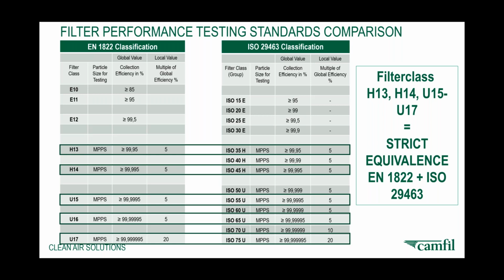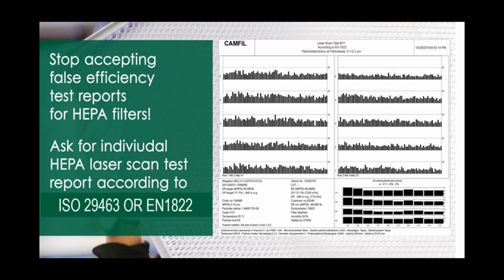And that's why the current recommendation from REHVA and other people is to try and use HEPAs where possible. But as mentioned in the document, they also say that it's important that you choose a HEPA filter carefully, and that some HEPA filters may not be suitable for the job that they're being asked to do. So when you're advising or recommending a HEPA filter to anybody, including the people you're going to help in buildings, ensure that it is tested according to EN 1822 or 29463, and importantly, that there is a test certificate given with the HEPA filter.